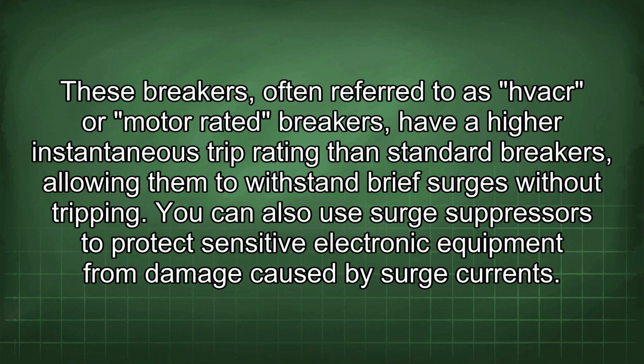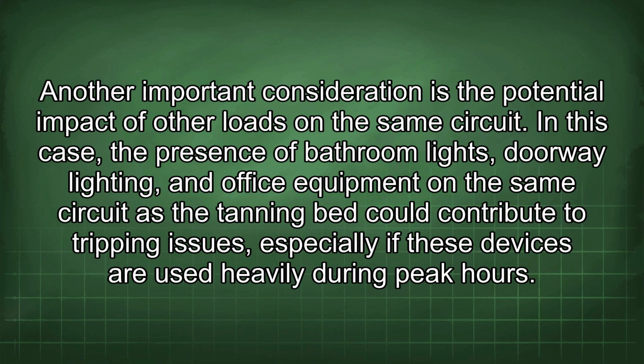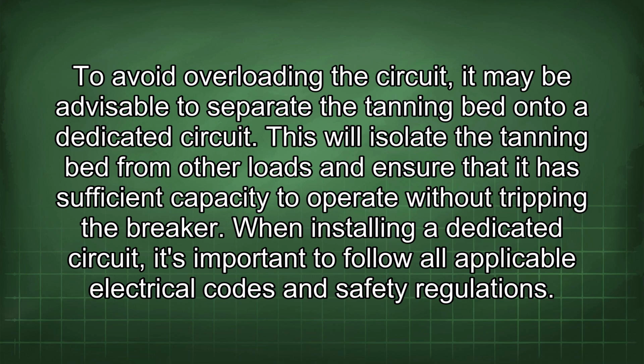You can also use surge suppressors to protect sensitive electronic equipment from damage caused by surge currents. Another important consideration is the potential impact of other loads on the same circuit. In this case, the presence of bathroom lights, doorway lighting, and office equipment on the same circuit as the tanning bed could contribute to tripping issues, especially if these devices are used heavily during peak hours. To avoid overloading the circuit, it may be advisable to separate the tanning bed onto a dedicated circuit.